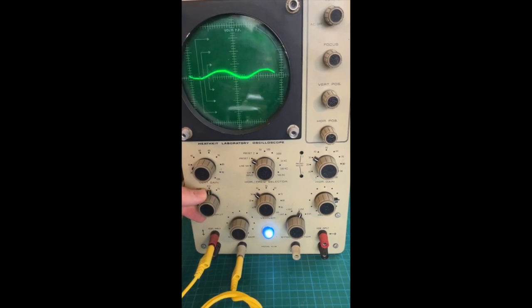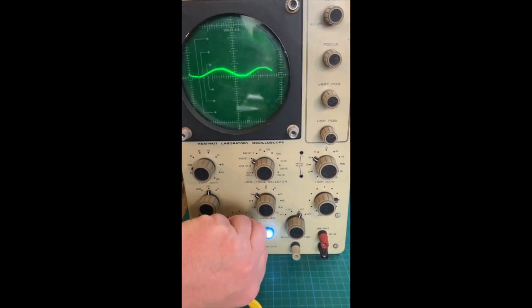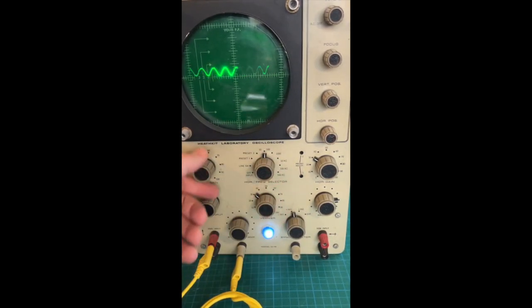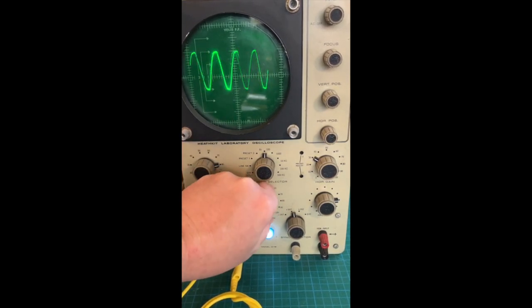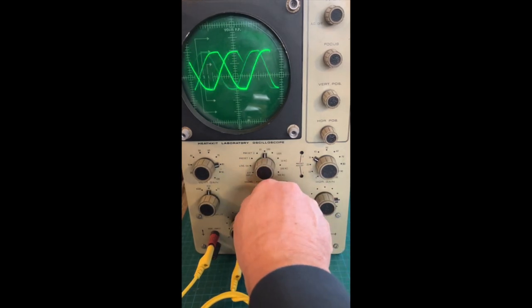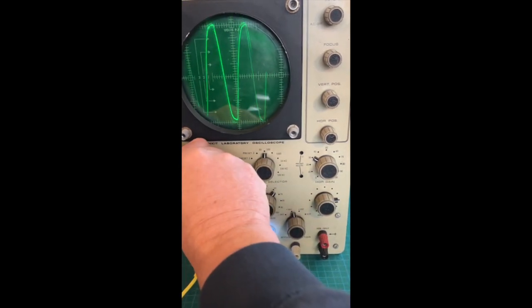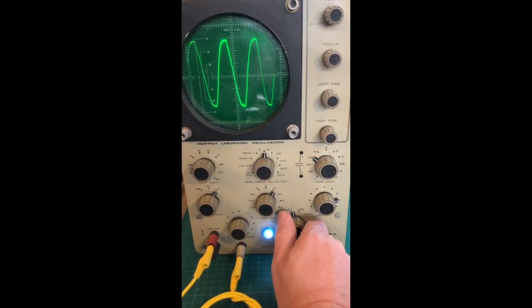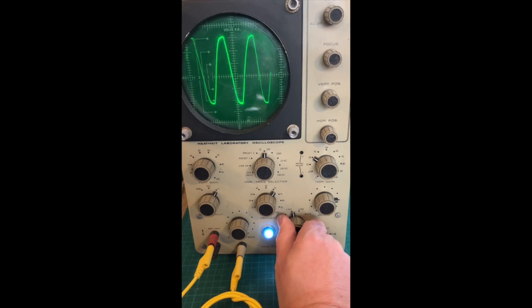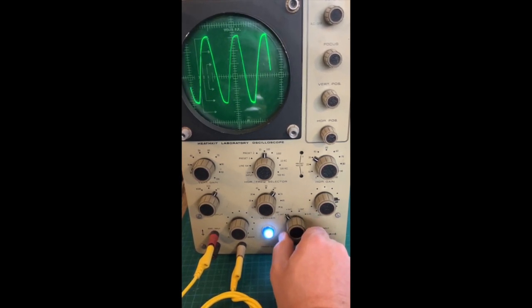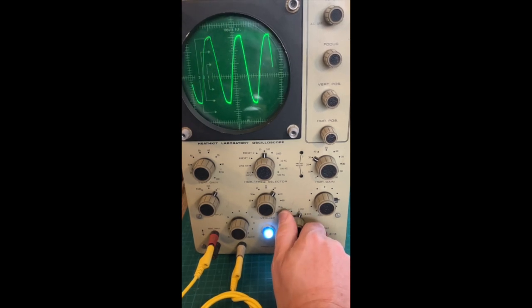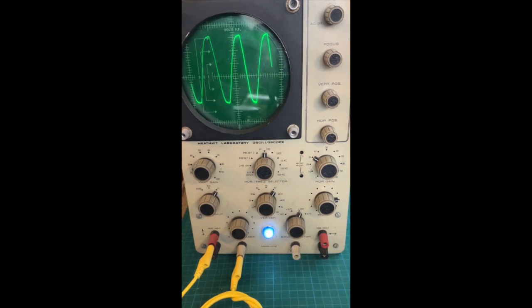An attenuator here, and the level of external sync you want, you can set here, as well as whether you want positive or negative sync. So if we go back to here, turn up the gain, turn up the frequency a little bit. Come on, go back to more gain. The sync signal can sync on the positive or negative going half of the cycle, or of course external sync, or line frequency sync. Line frequency sync is the same as the others here because we're just looking at line frequency. And that in a nutshell is basically the controls of this IO-18.